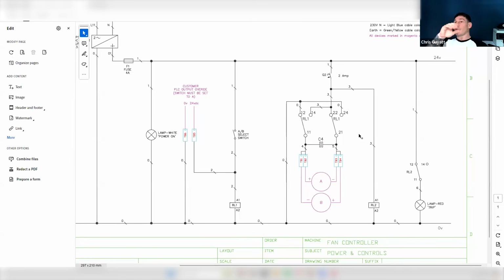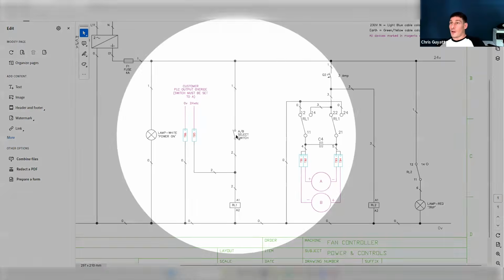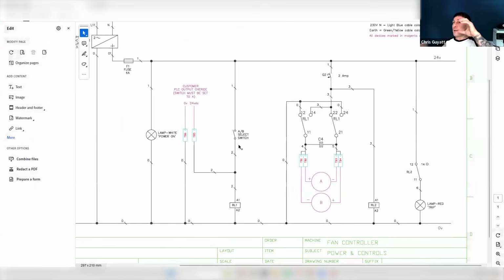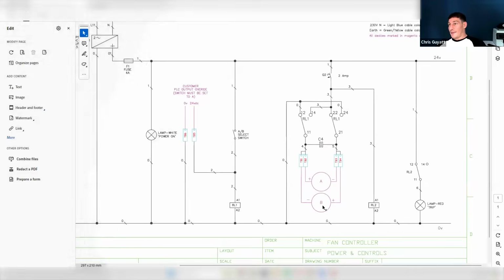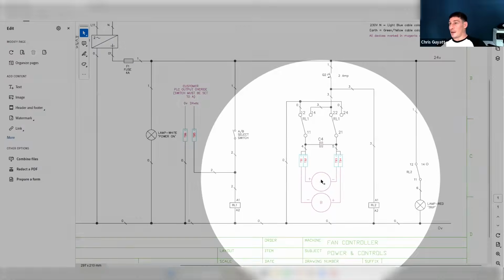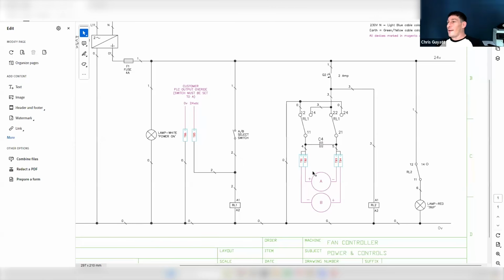When we want to be able to, just through a switch on the front of the panel that you can see here, A/B, when it's in one position, A, we want damper A, which is indicated here, open, and damper B closed. And then when I change that selector switch to B, we want the reverse to happen, so we want A to close and B to open. And to achieve that, that's kind of how we're doing the control through this relay here.